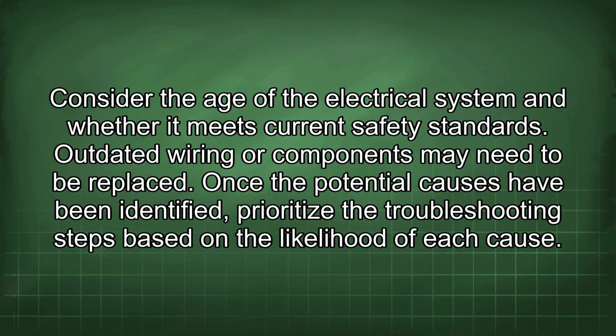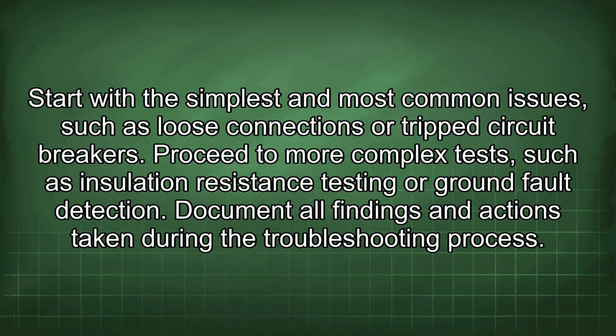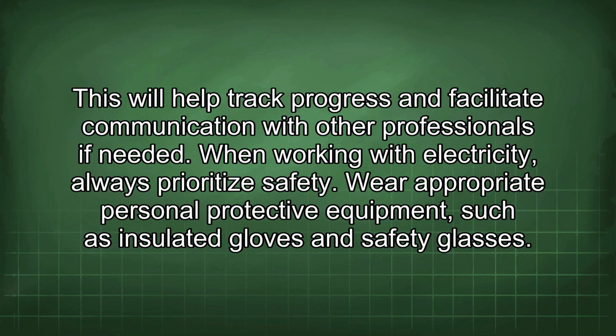Once the potential causes have been identified, prioritize the troubleshooting steps based on the likelihood of each cause. Start with the simplest and most common issues, such as loose connections or tripped circuit breakers. Proceed to more complex tests, such as insulation resistance testing or ground fault detection. Document all findings and actions taken during the troubleshooting process. This will help track progress and facilitate communication with other professionals if needed.